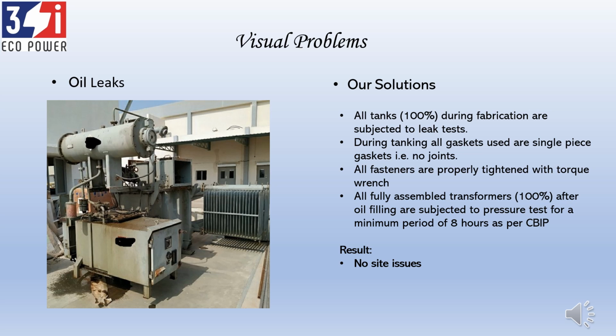Once we receive the tanks at the factory, during the process of making a transformer, all the gaskets we use are single-piece gaskets - there are no joints. Most commonly, people buy gaskets in rolls and do dovetail or butt joints, then bolt them. But if there are joints, once pressure is applied, there's every chance the joints may crack.